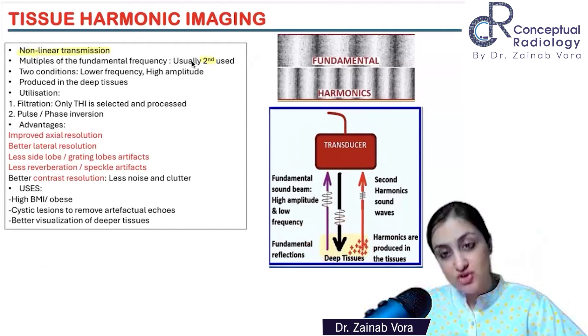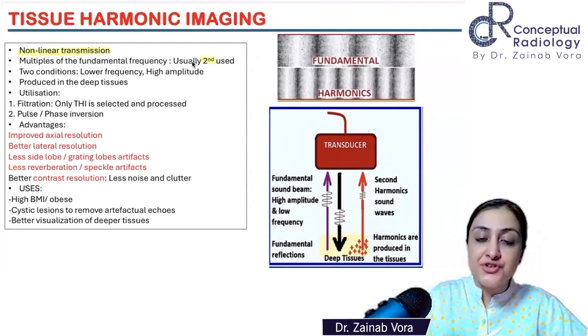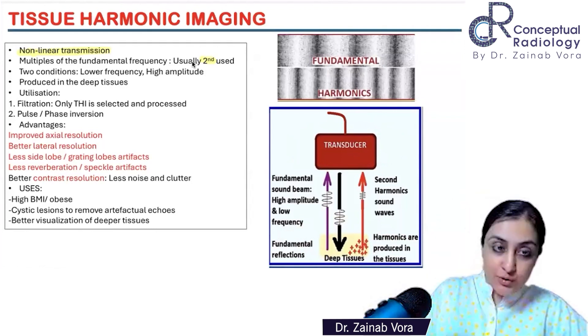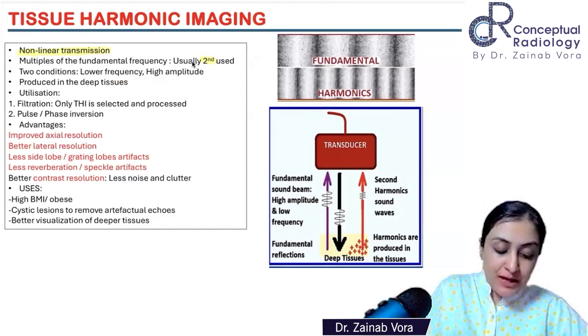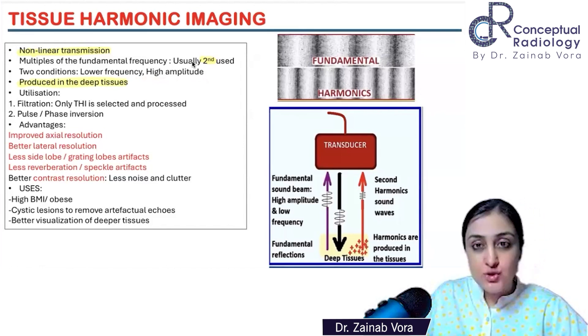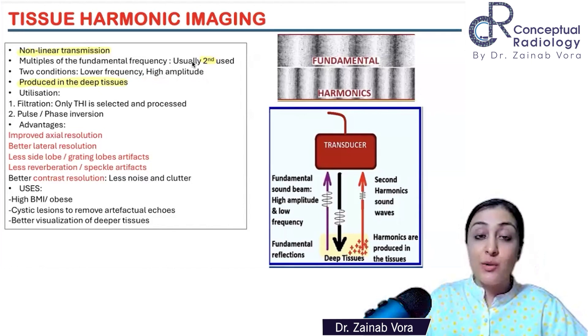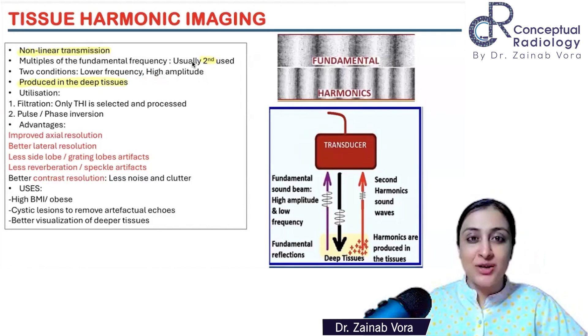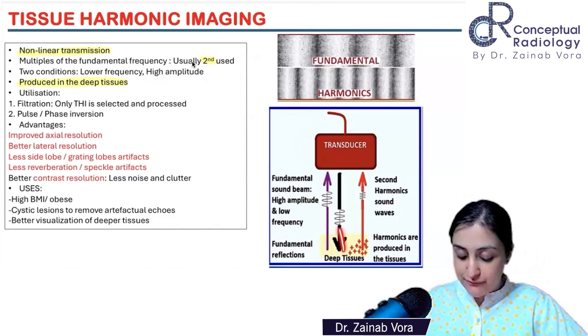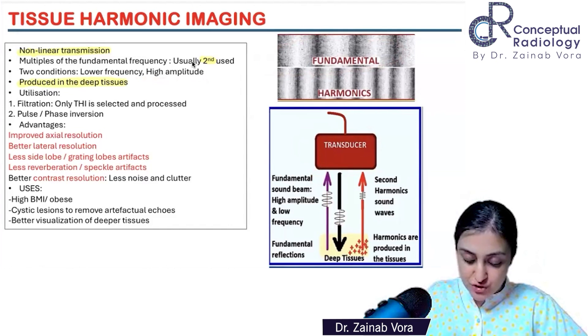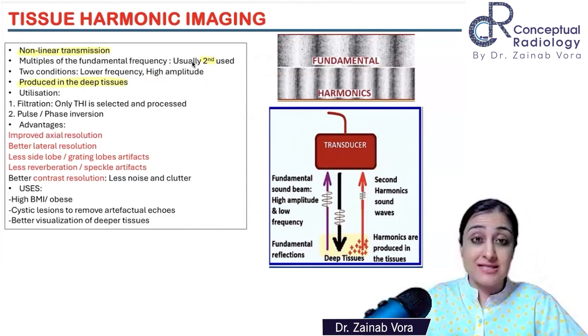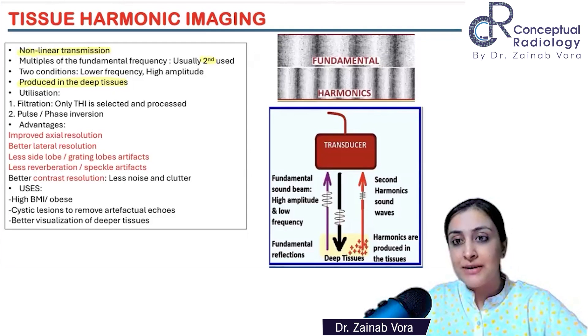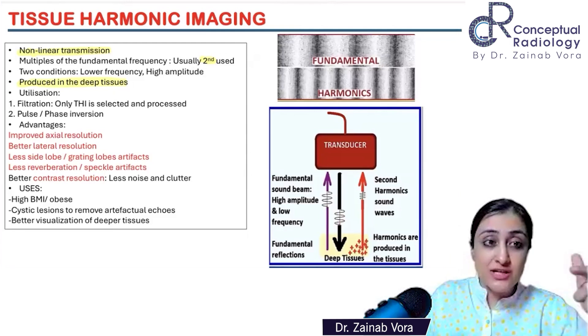Harmonics are physiological — it's not something the transducer generates. The advances are that we are now able to pick up the harmonics. What you need to remember is that harmonics are generated by the tissue, and it's the deeper tissues that generate them. Two conditions: they are low frequency and high amplitude. We are interested in a lower frequency for harmonic imaging. They are not produced by the transducer — they are produced by the deep tissue itself. There is a separate knob or button for this on all machines.